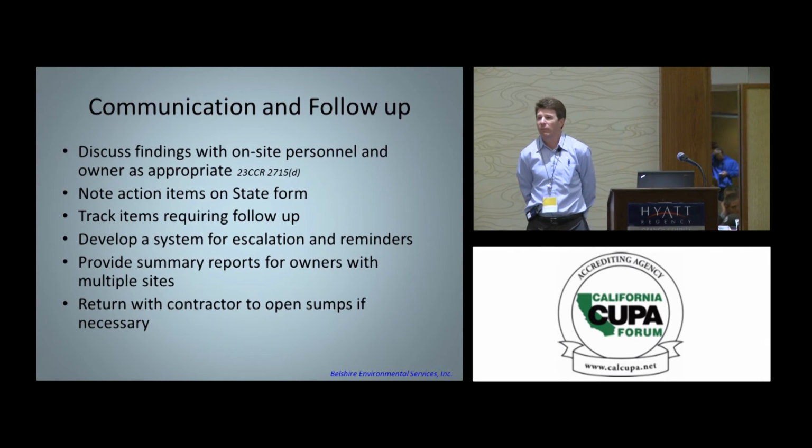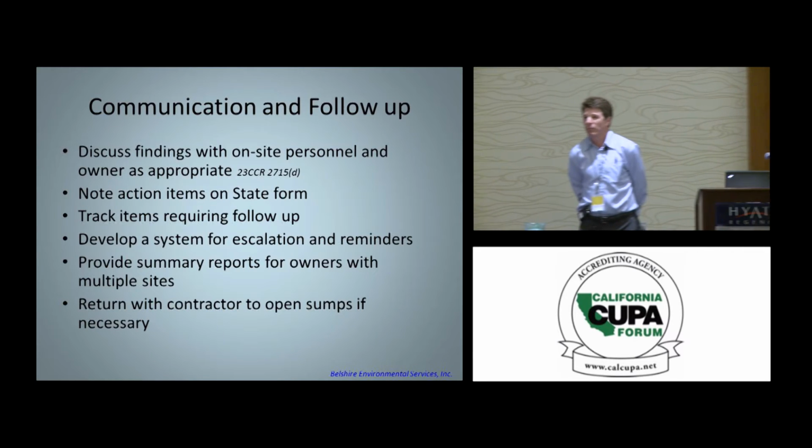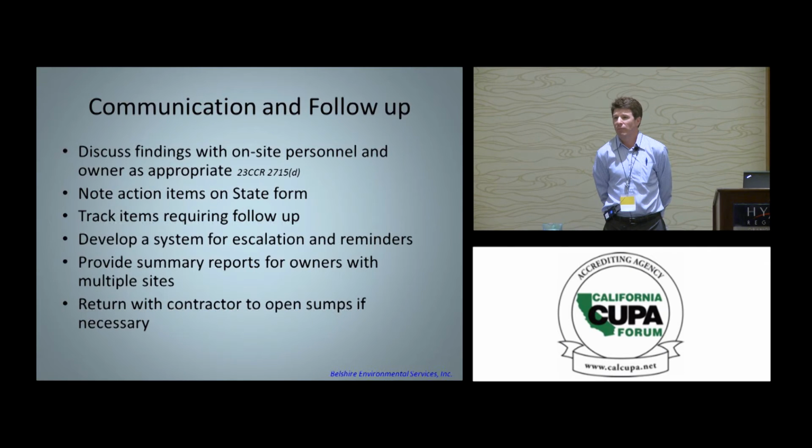So I think the conundrum, too, is that the DO is responsible to, it says in 2715, they have to say that it's in the lowest place, but where does it say for a new tank system like a VPH? We've recently looked all over the regs for this. Where does it say that sensor has to be at the lowest place, where the liability is on the owner-operator, or the licensed technician? It doesn't specifically say that. You can take it back to construction where it says detect a liquid at the earliest opportunity, but there's no language in there for what I call super new tank systems, for a sensor to be at the lowest point, except for the DO to look for it.